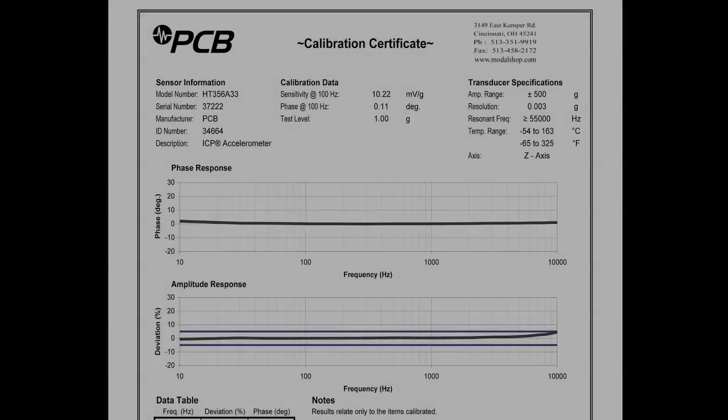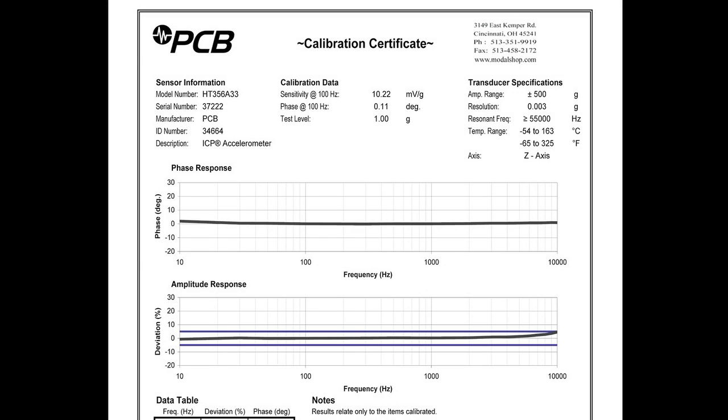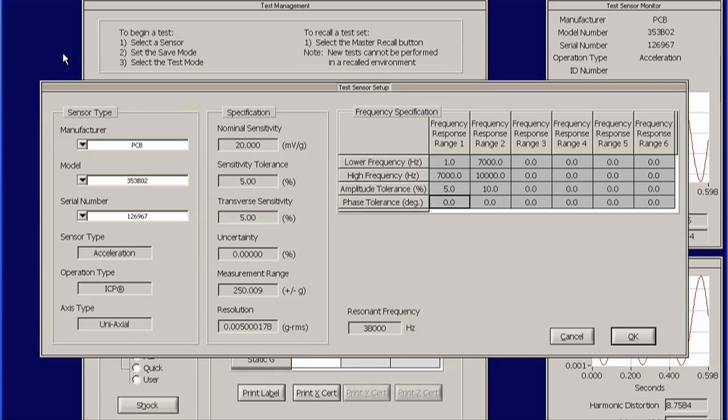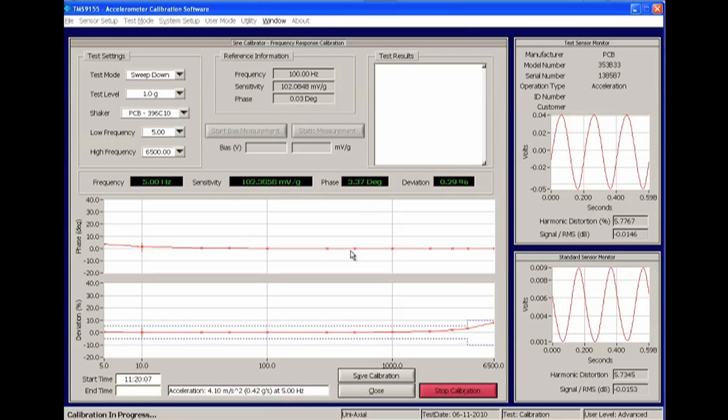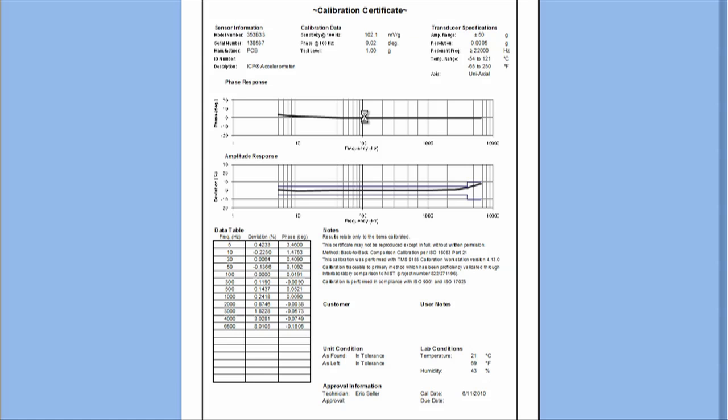Running a frequency response calibration is a quick, simple process. Once the sensor is mounted and connected to the system, completing the calibration involves three steps: 1. Select the sensor that is being calibrated and the test being used. 2. Run the calibration. 3. Save and print the calibration results.